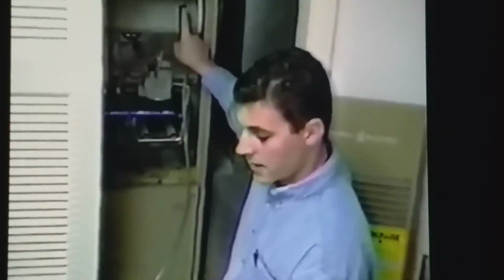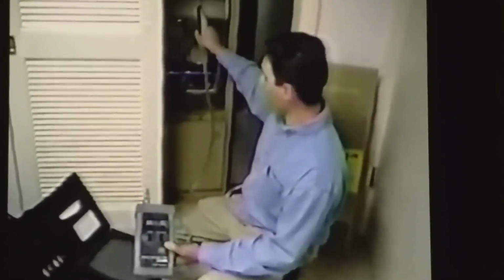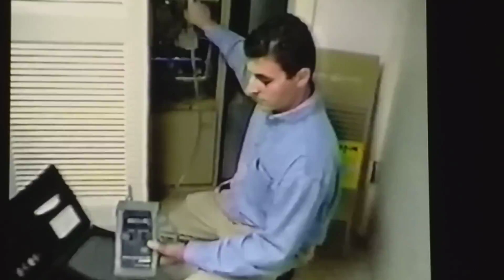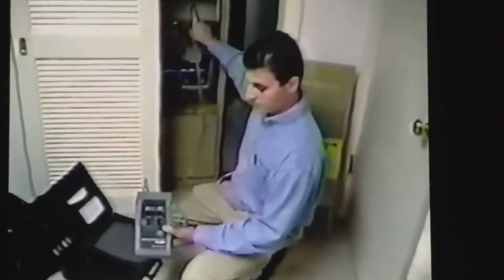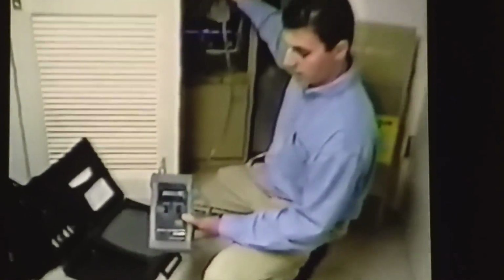So we're going to let that climb until it stops and kind of levels off. Here it's going back down. Check the next chamber over. There's 3 chambers, 3 burners, so there's 3 cells of the heat exchanger. Now this one's climbing very, very high at this point.